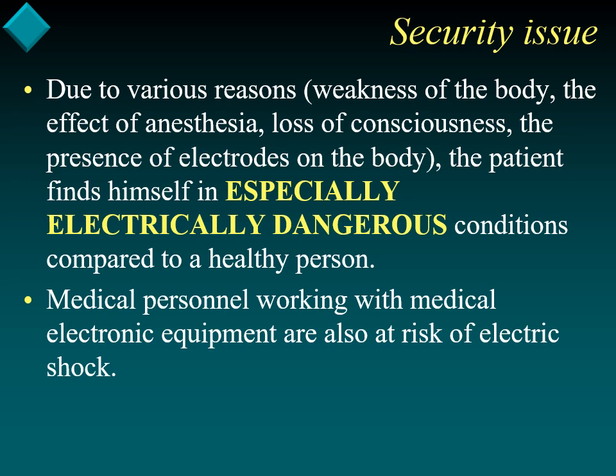In comparison with a healthy person, the patient sometimes finds himself in particularly electrohazardous conditions for a number of reasons: weakening of the body, lack of consciousness, or the presence of electrodes on the patient's body, which is intentionally exposed to current, directly connected to a DC circuit, either low-frequency or high-frequency current.